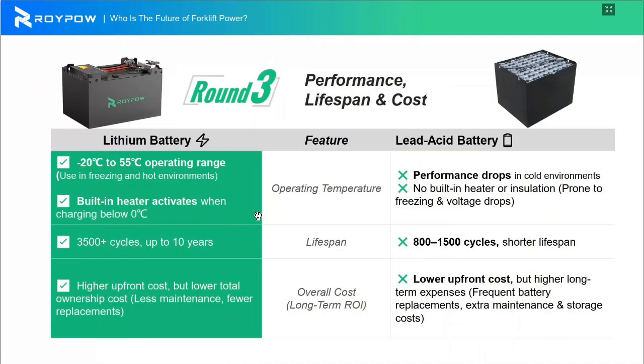Round three: performance, lifespan, and cost. A lithium battery has a wide operating temperature range, supporting minus 20 degrees Celsius to 55 degrees Celsius. You can use the battery in both a freezer or extreme hot environments like Dubai or Thailand. It has a built-in heater that activates when charging below 0 degrees Celsius, and it supports 3,500 cycles, with a design life that can reach up to 10 years.